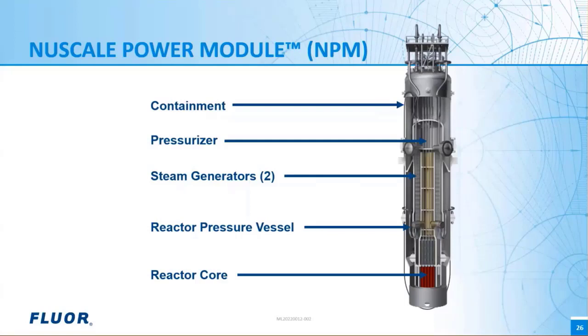Reactor coolant at the bottom where the reactor is goes through the core where uranium fuel fissions and heats the primary coolant. That primary coolant flows up through a riser above the core, and it rises due to reduced density, flows out into the two steam generators located on either side of the riser, where it transfers its heat to the secondary water loop that's inside the steam generator tubes. And then superheated secondary loop steam leaves the power module and the reactor building, goes to the turbine generators, and drives the generator as we discussed earlier. Pressurizer is located above the riser, inside the reactor vessel and inside containment.